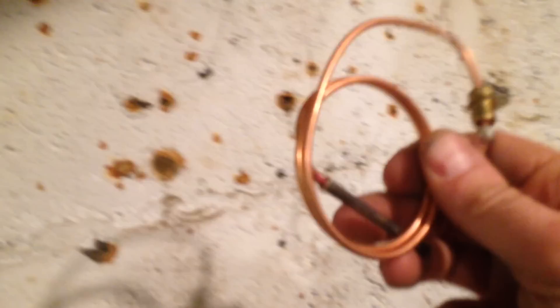I also want to point out I have some spare thermocouples here just in case. This one is actually for the hot water heater. This one is more like a thermopile, because that's what's in the boiler now — it also has different threads than the conventional thermocouple for the hot water heater. So I have both on hand just in case there's a problem with the pilot.